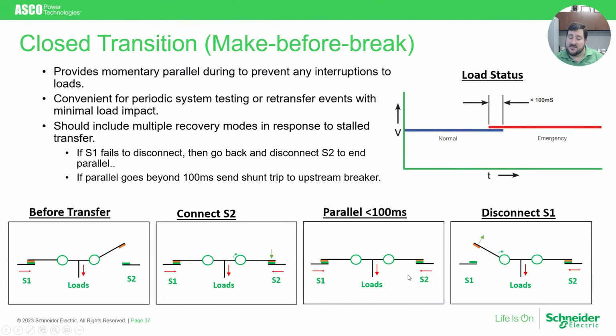Now, the great thing about this is that it means that during a retransfer or a test, your loads are not exposed to any outage whatsoever, and these transitions can happen transparent to anyone in the facility or the loads. It's very effective. However, for it to happen, like I mentioned, there are several rules that have to be followed.